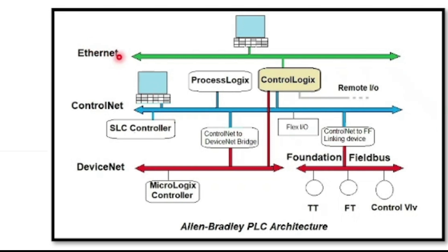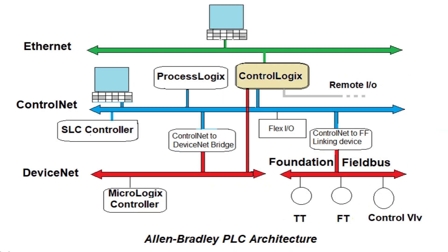With NetLinx we can define three types of networks: Ethernet, ControlNet, and DeviceNet. The ControlLogix controller can communicate via a backplane communication interface module to monitor and control IOs on ControlNet, DeviceNet, and Ethernet. ControlNet is an open, high-speed network used for transferring data and provides real-time control and messaging services for peer communication.